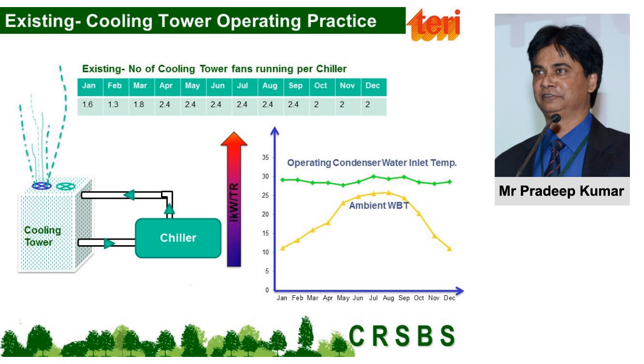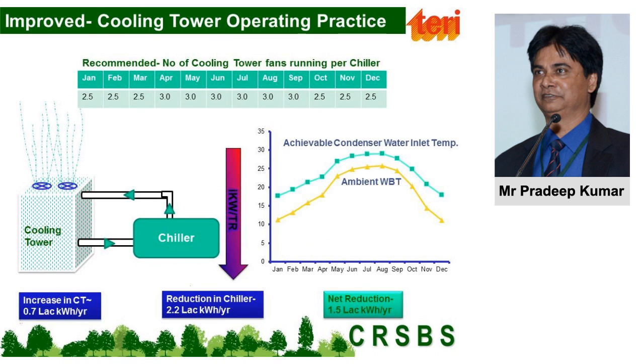And then we had a discussion with the maintenance team. They said that, okay, they only look at the temperature of the condenser water in, and the moment it comes down to 28, they switch off these fans. And if you remember a graph I showed you, that was the chiller one, lower the condenser water in temperature, better is the efficiency. We worked out and we said that, okay, in order to maximize this, or take advantage of wet bulb depression, more cooling towers need to be operated, and it should be operated in this fashion.